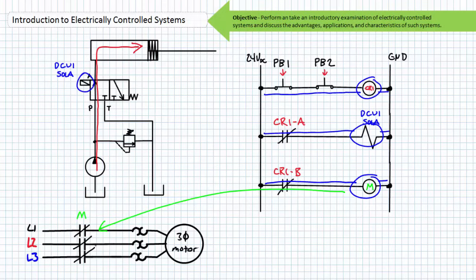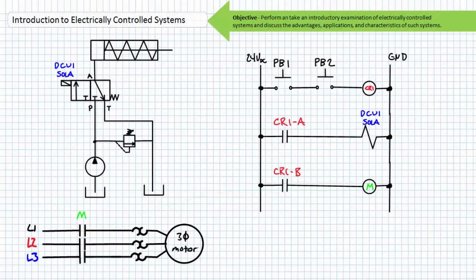The hardwired connections or programmed instructions internal to the ladder logic can perform numerous other functions, including but not limited to latching, unlatching, interlocking, sequencing, counting, comparing, coordinating, communicating, and timing operations. Let's return to close out our earlier discussion about troubleshooting an electrically controlled system.